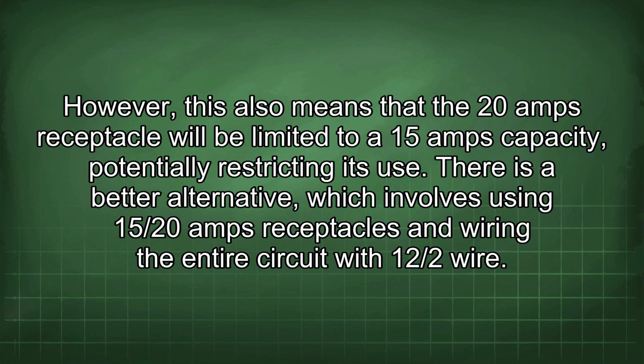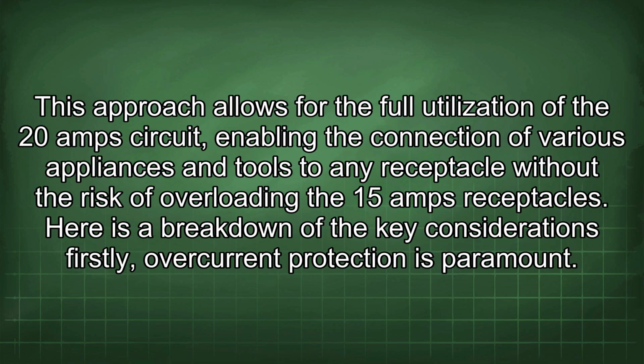There is a better alternative, which involves using 15/20 amps receptacles and wiring the entire circuit with 12/2 wire. This approach allows for the full utilization of the 20 amp circuit, enabling the connection of various appliances and tools to any receptacle without the risk of overloading the 15 amps receptacles.